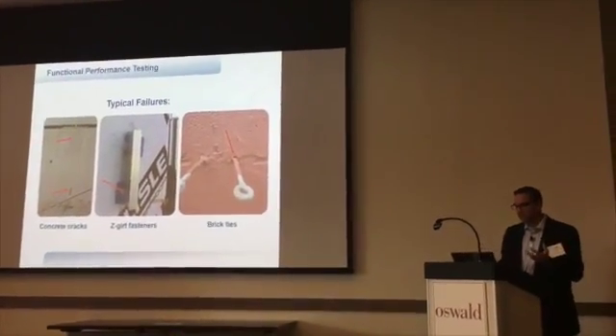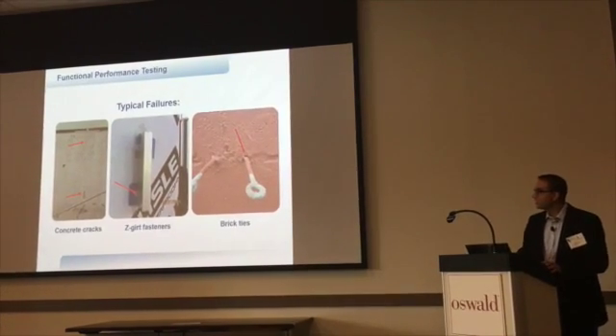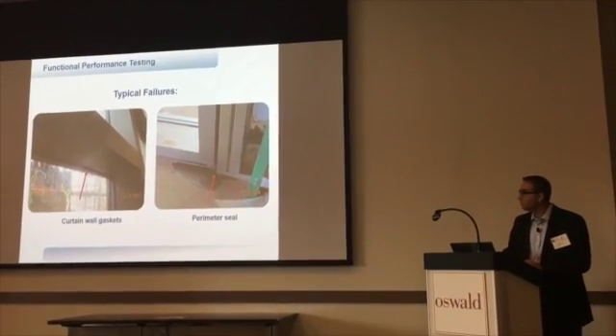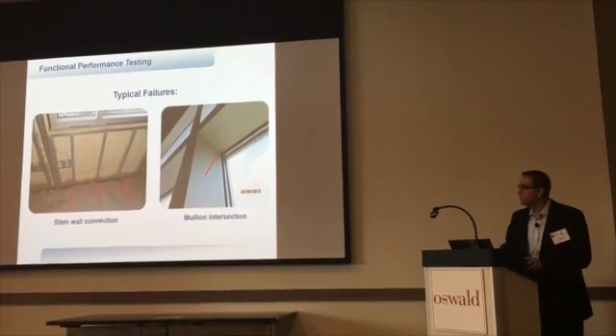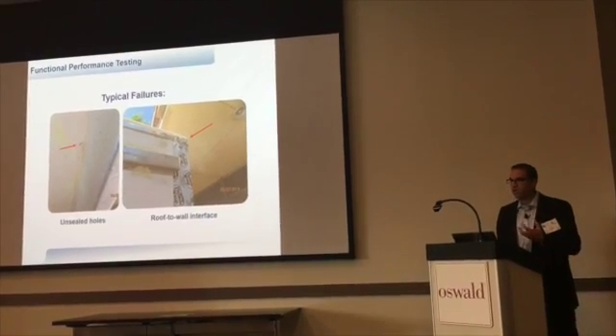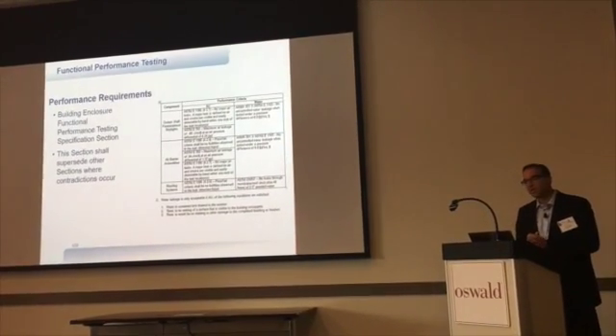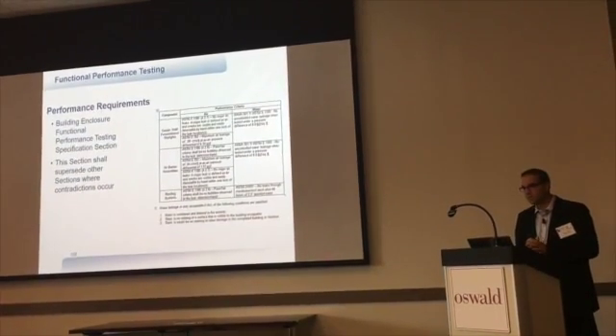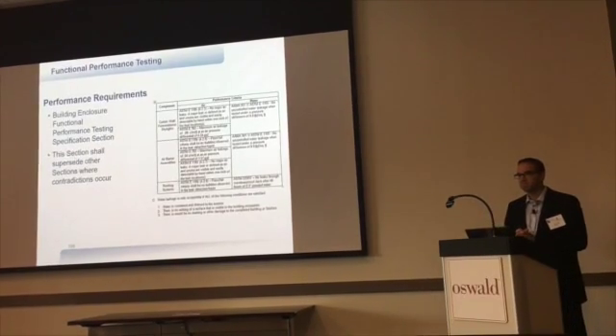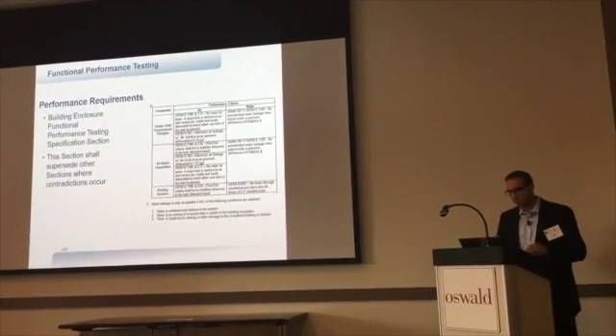When writing a test procedure, you have to know how things fail. If we have a masonry tie in a fluid-applied coating and know they're going to move the tie and might break it, we have to think about how to test that in the field. If we're worried about glazing leaks, how do we test that in the field? What's the best way to look at these intersections and different components coming together? A lot of our tests do not have pass-fail criteria within the ASTM standard. So if you say 'go do this test' and it doesn't have pass-fail criteria, the contractor is not going to respond to a poor test result — they'll just say, 'Thanks, job done, good information, we're moving forward.' You have to build that pass-fail criteria into the commissioning spec.